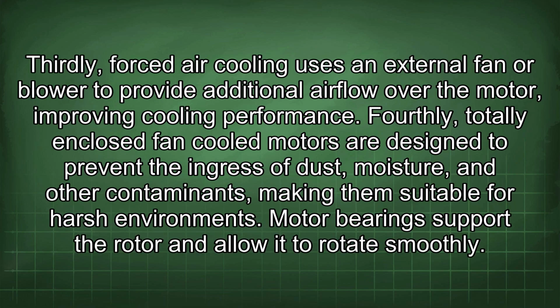Thirdly, forced air cooling uses an external fan or blower to provide additional airflow over the motor, improving cooling performance. Fourthly, totally enclosed fan-cooled motors are designed to prevent the ingress of dust, moisture, and other contaminants, making them suitable for harsh environments. Motor bearings support the rotor and allow it to rotate smoothly.